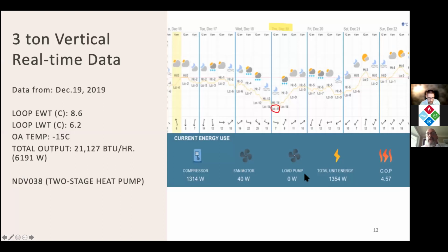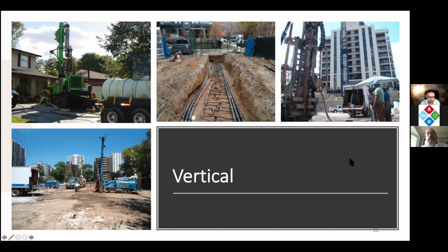Also in that middle slide that you can't see, with the vertical bore especially, you definitely need to grout, because one thing you don't want is airspace or pockets in that vertical bore. Everything's got to be tight around the loop to have proper heat transfer, so you can get the BTUs you need for the unit to supply heating and air conditioning for the space. So grouting is key - very, very good point.